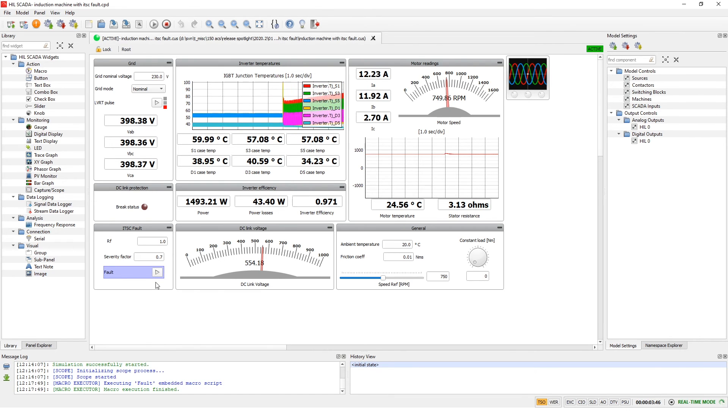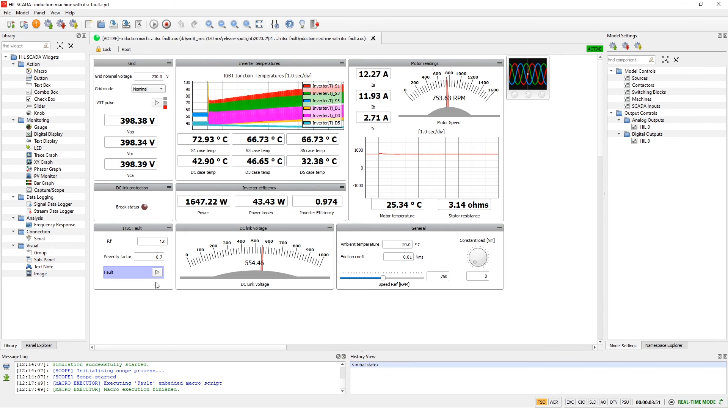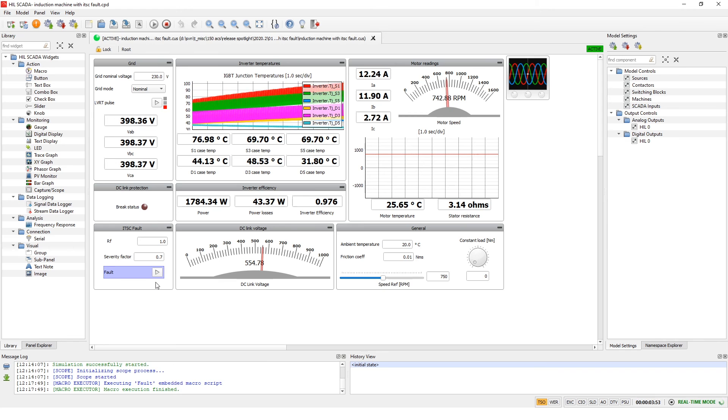First of all, speed will become much more unstable and the IGBT junction temperatures will rise, and also currents will become highly unbalanced.